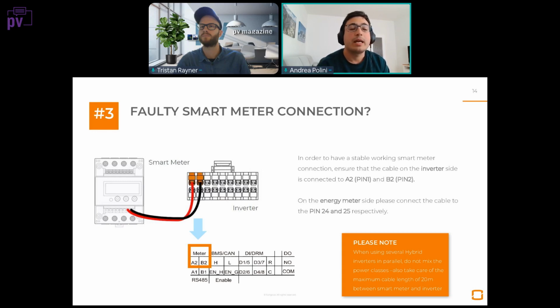And the energy meter from Chint, this one, the three-phase one, has an option of also connecting a 120 ohm termination resistance to equalize the communication, the transmission channel, and to make the signal move better and without issues throughout the cable. This is done by connecting a short circuit, a small cable, between the pins 16 and 17 of the smart meter. And this we have found helps quite significantly in this kind of smart meter connection issues.